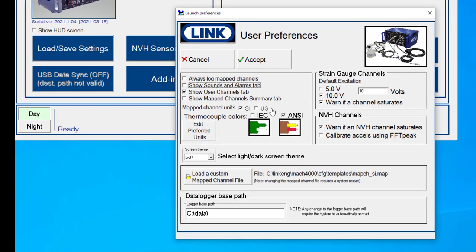When you go in the user preferences, it gives you a place to set up your default analog channel excitation voltage. So for example, most of the sensors that I presently use are all 10 volt. If I had a mixture of lower voltages, I could program that in to make sure that those sensors never have too much excitation voltage when the rack first powers itself up.